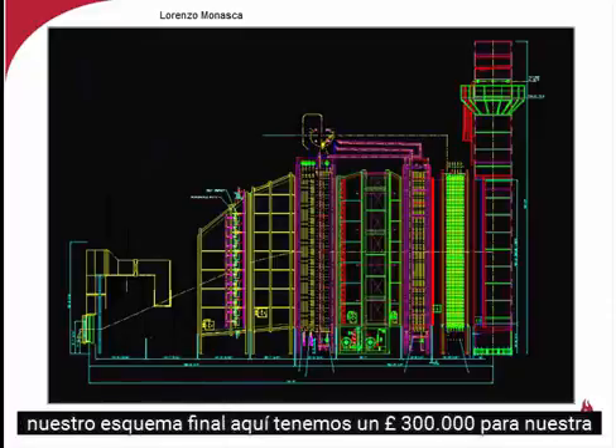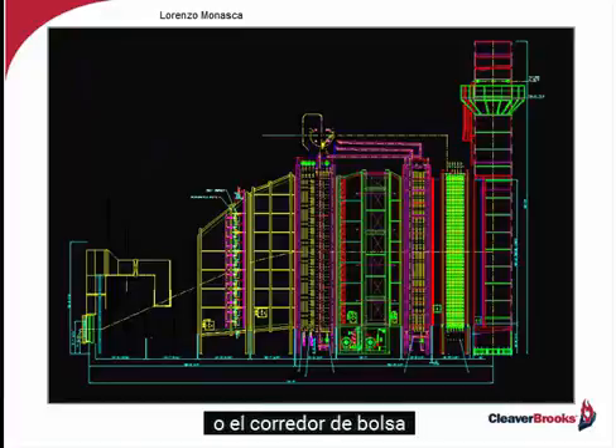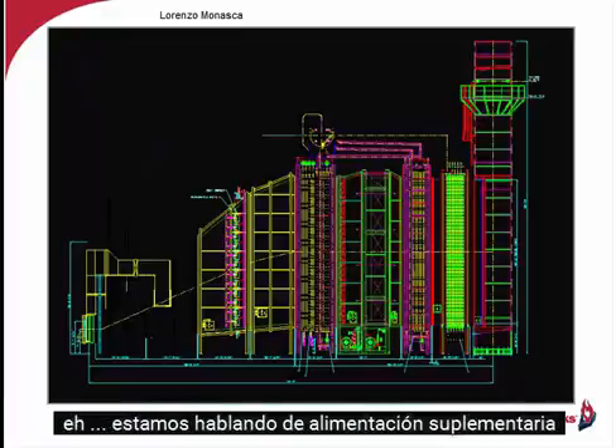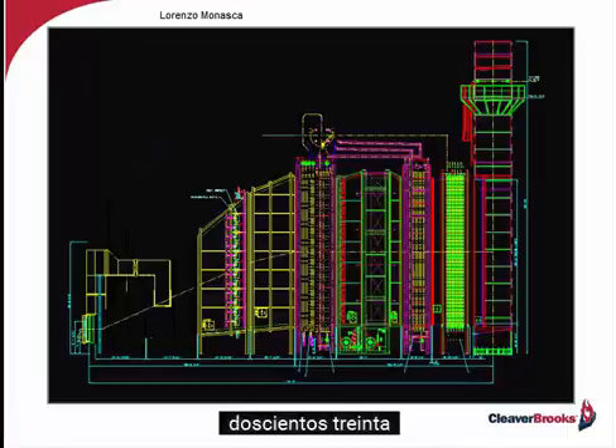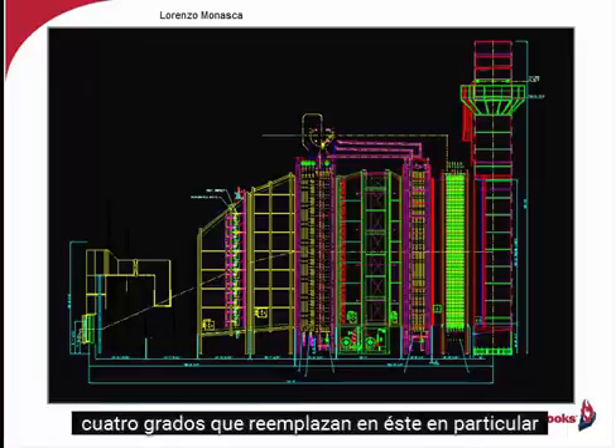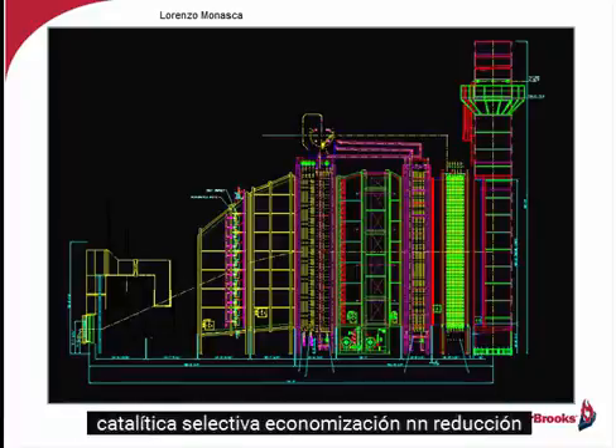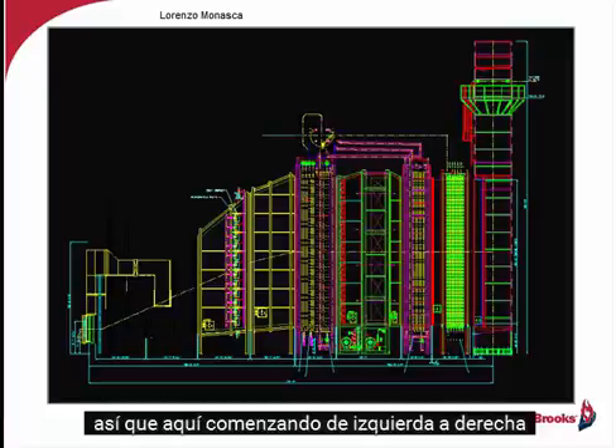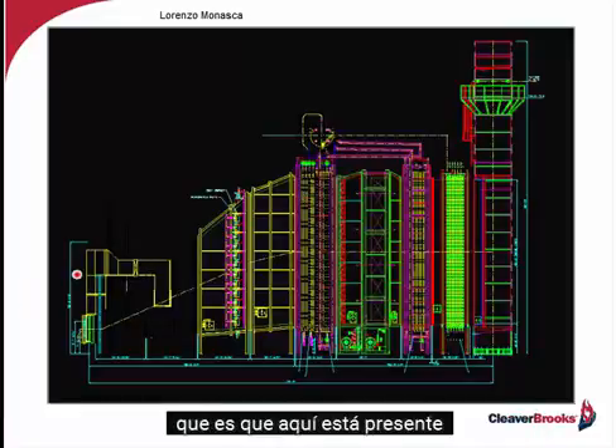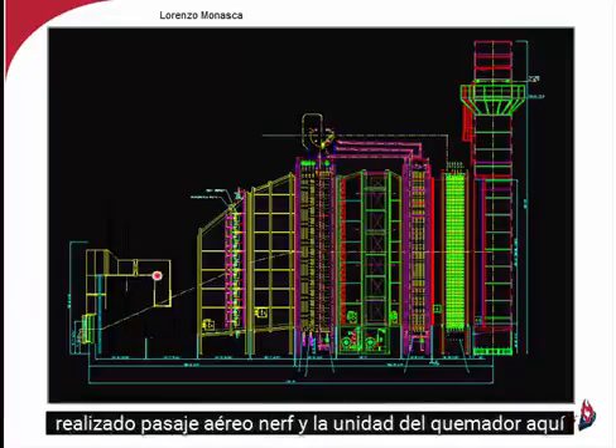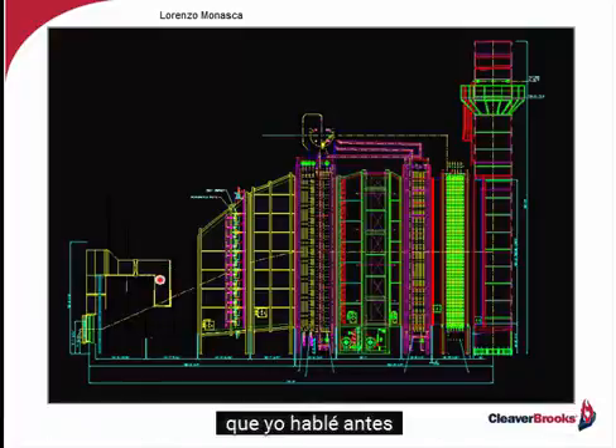Now our final schematic here, we've got a 300,000 pound per hour system with a duct burner. We're talking supplementary firing, 234 degrees of superheat in this particular one, selective catalytic reduction, and an economizer. So starting here from left to right, what you see right here is this combustion air fan or fan burner assembly right here that I spoke of earlier.